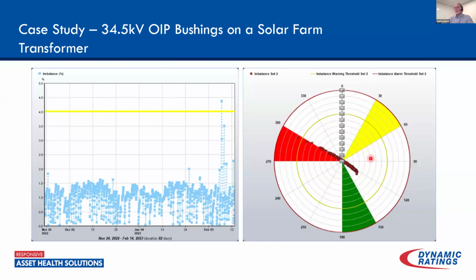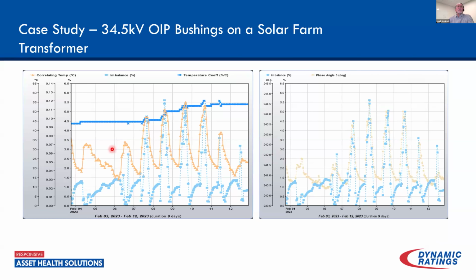this is more of what I would expect to see when I have a bushing degrading. For the most part, it's got a pattern, it tends to follow, and I start seeing a few points that exceed my warning threshold here. And then sure enough, as I dig into that data more, with OIP bushings, one of the biggest things we see is that as they fail, they tend to get an increase in moisture ingress. That increase in moisture ingress results in an increased temperature coefficient in the bushing.